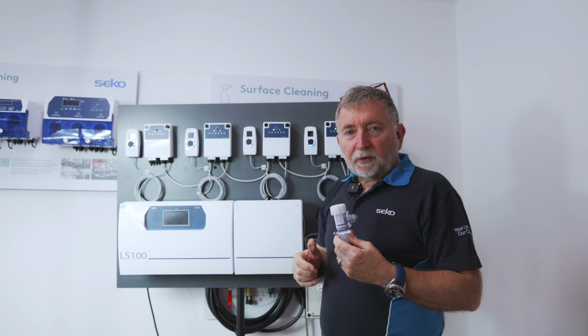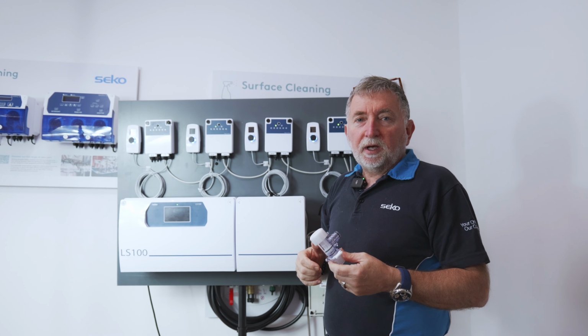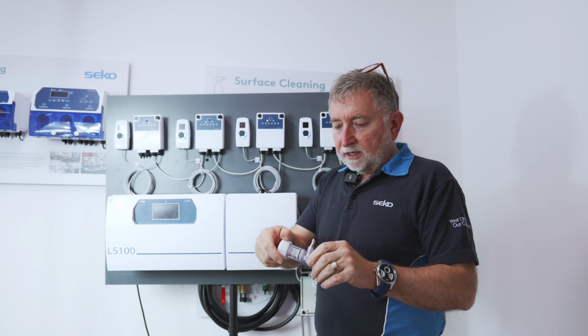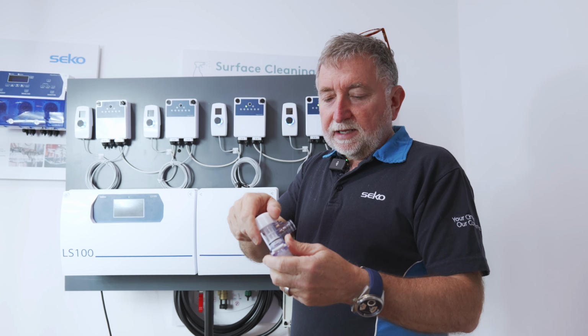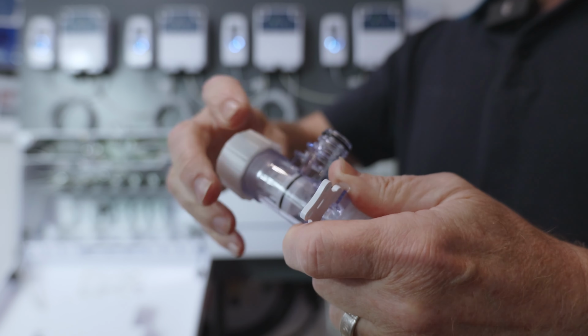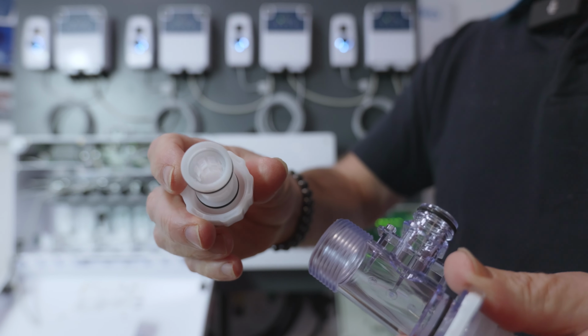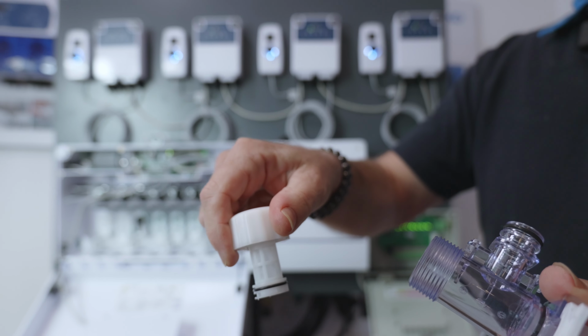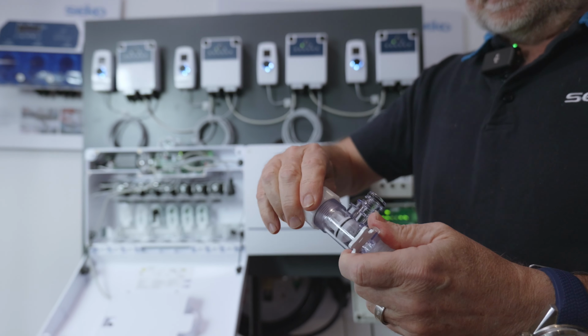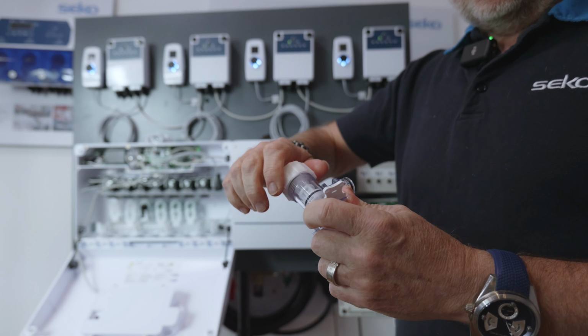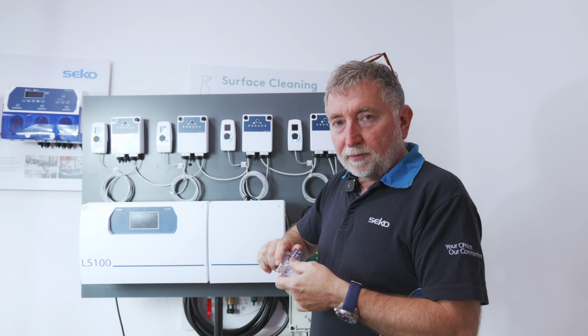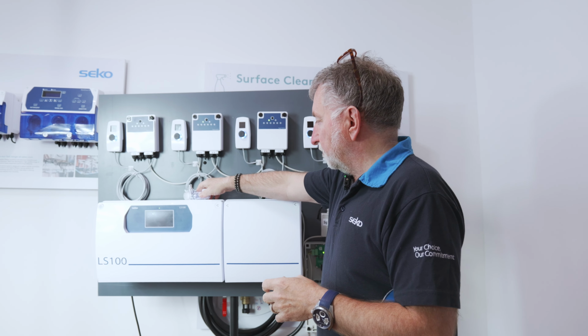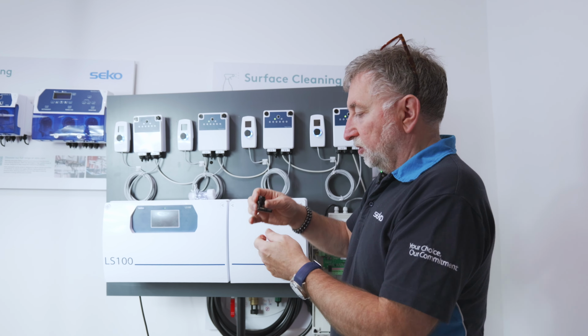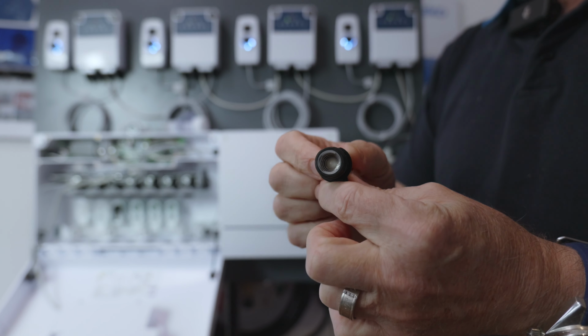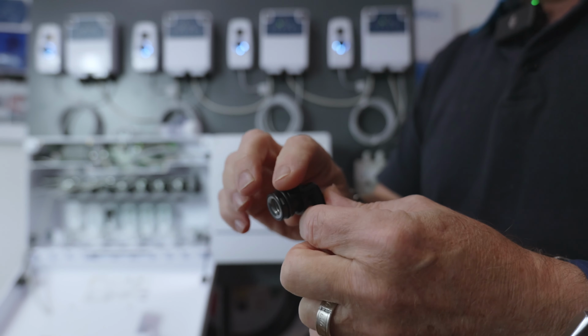So as we've mentioned, there's very little maintenance with the LS100, but there are some things to check periodically. The filter on the water inlet can be removed and cleaned. Simply unscrewing that and just giving it a wash around in some water to get rid of some debris that may have accumulated in there. If you have an issue with any of the chemical suction, if you notice your flow rates dropping or you're receiving alarms, you can remove the check valve, and again that can just be flushed in some hot water.